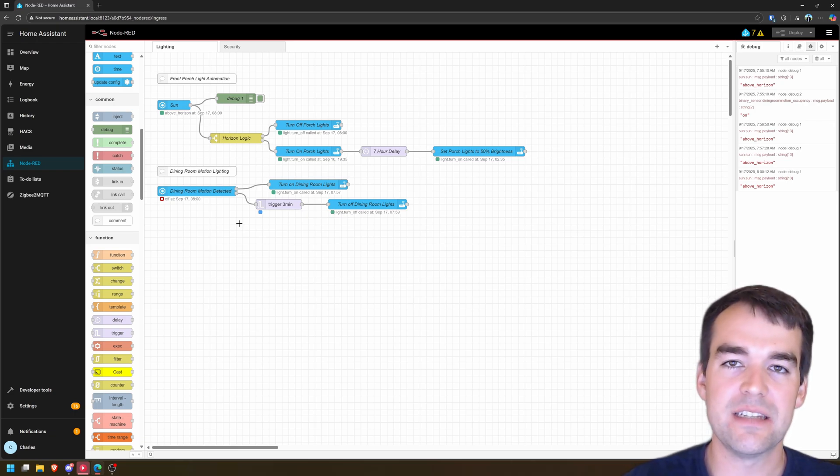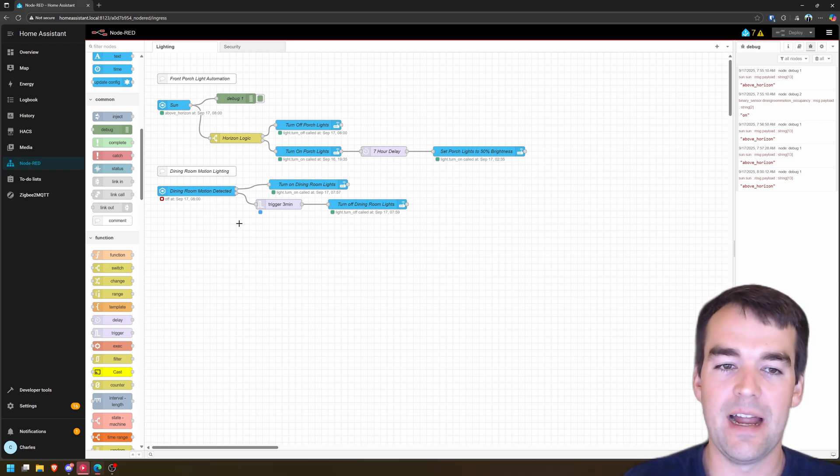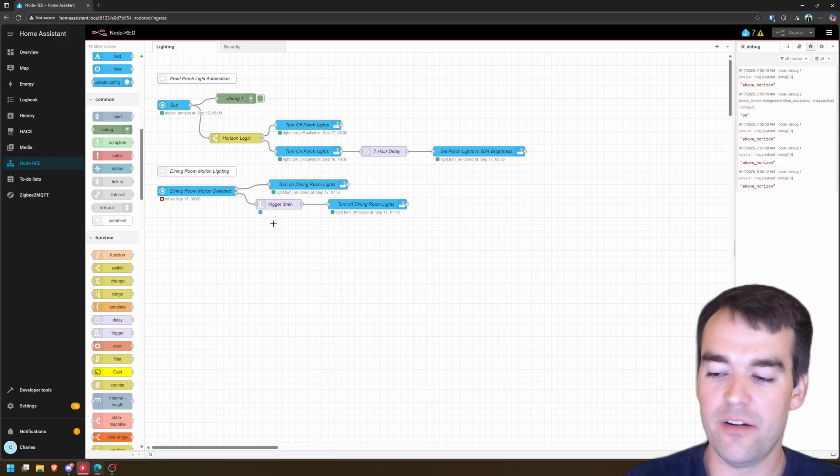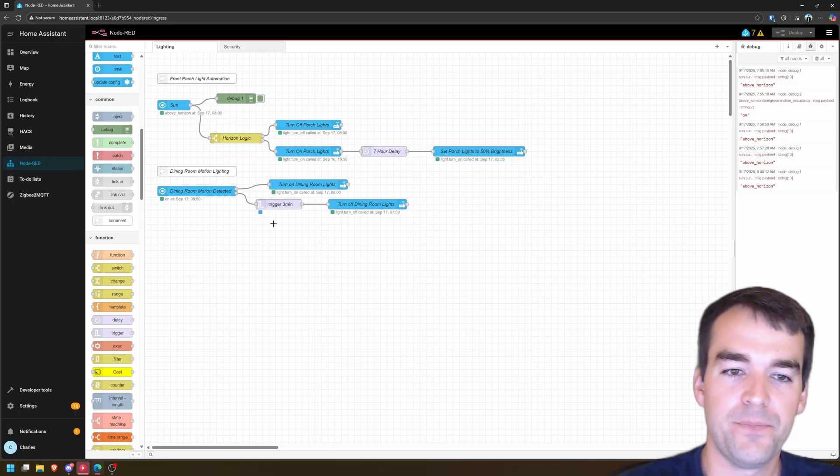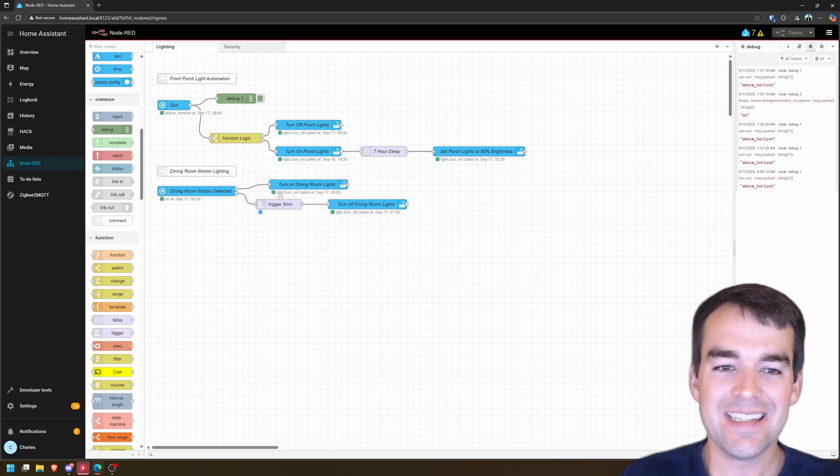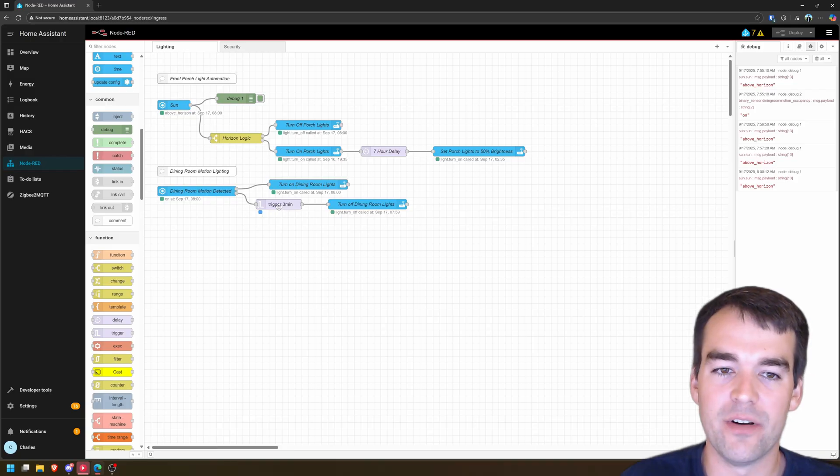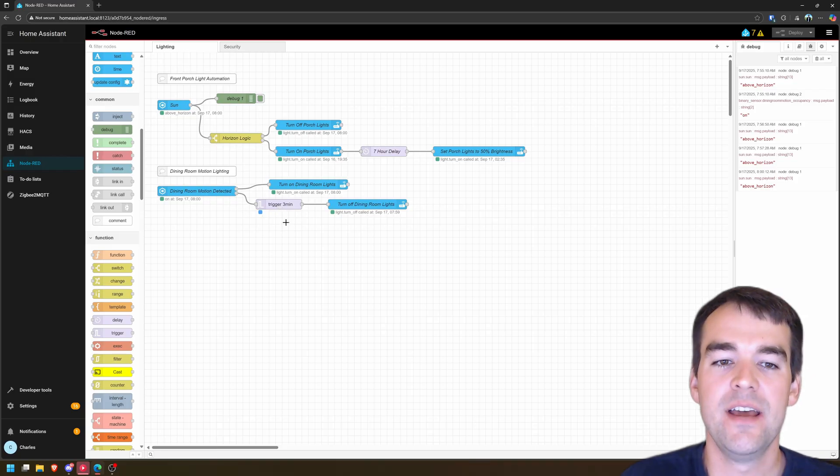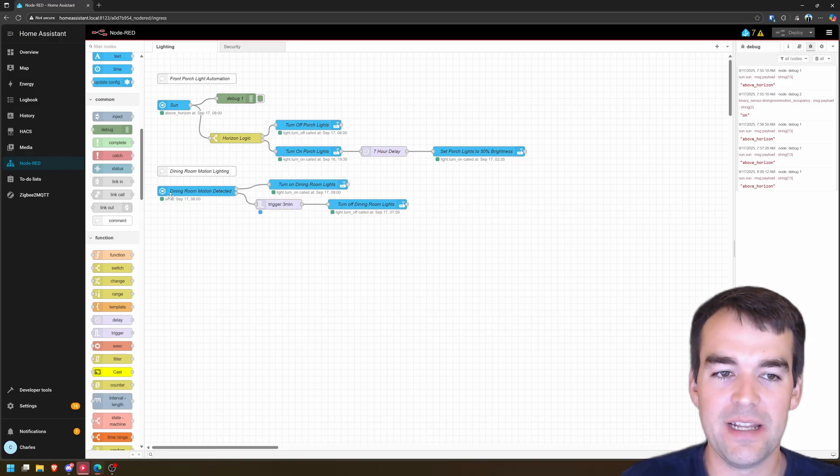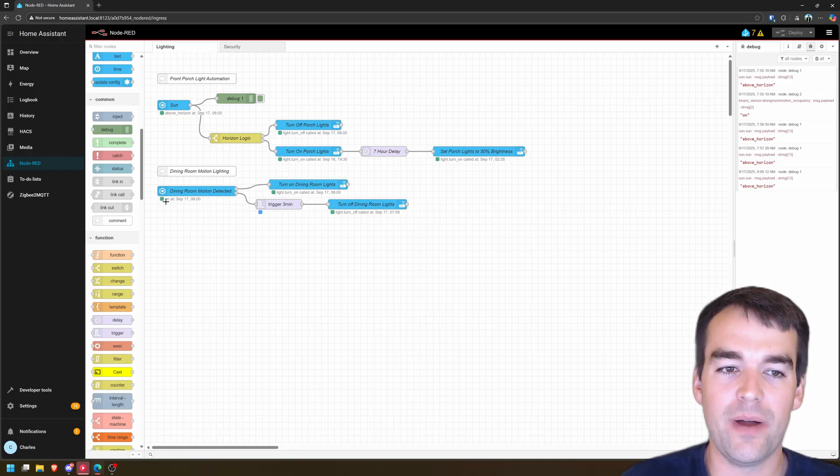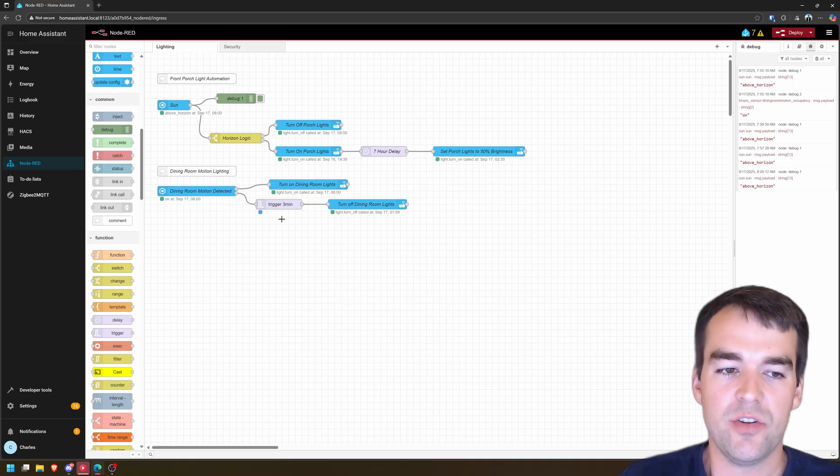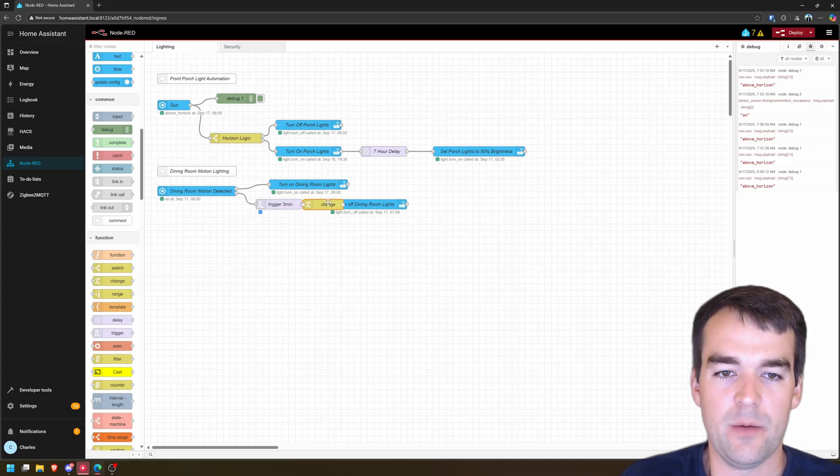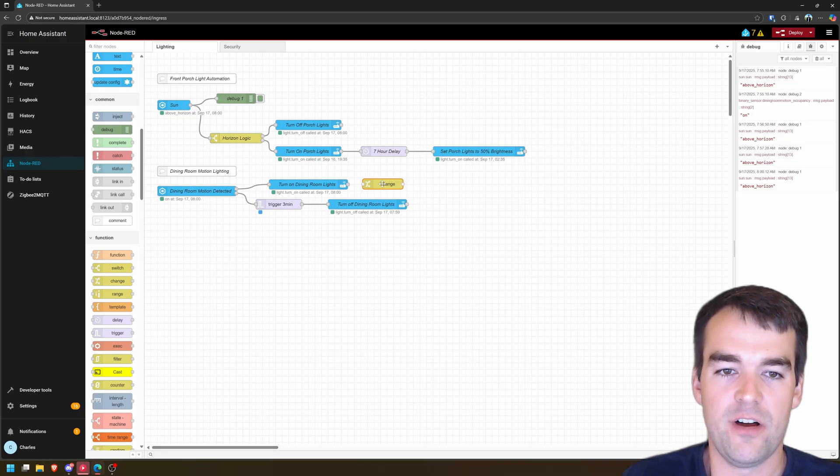And this automation is getting close to what we want to do that when you are in the room, the lights are on, you leave the room, it waits a second and then it turns off. That waiting is very helpful that if you're walking around in front of the motion sensor and it doesn't see for a minute and a half, it sees you again. It's going to delay that turning off the room lights. But what this doesn't cover is while this timer is going off, if it sees me again, if I turn the motion around, it doesn't cancel that trigger timer of three minutes.